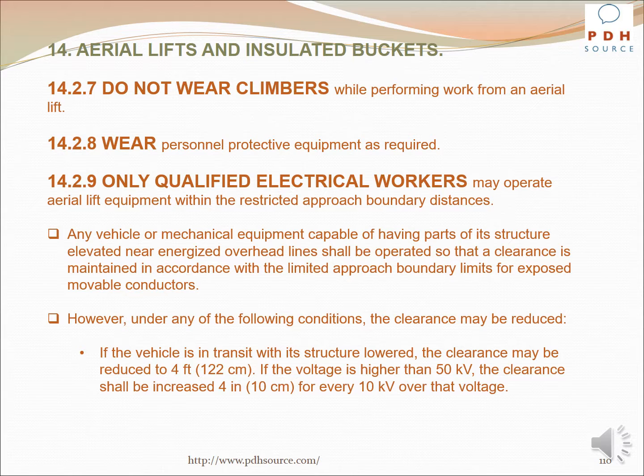However, under any of the following conditions, the clearance may be reduced. If the vehicle is in transit with its structure lowered, the clearance may be reduced to 4 feet. If the voltage is higher than 50 kV, the clearance shall be increased 4 inches for every 10 kV over that voltage.